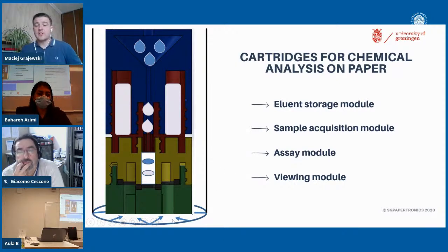These blue arrows indicate the concentrator at work. The concentrator works in two ways. One way is to make sure that the entire collected sample is analyzed. So all the liquid trapped here has to finally travel to the end and will be evaporated. But it also works as an accelerator of the reaction because we actively evaporate. So instead of waiting for everything to seep through, we accelerate the reaction by a factor of 10 at least, depending on the packaging of the column.